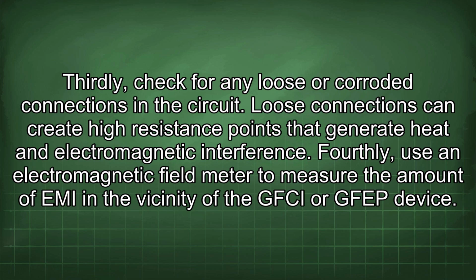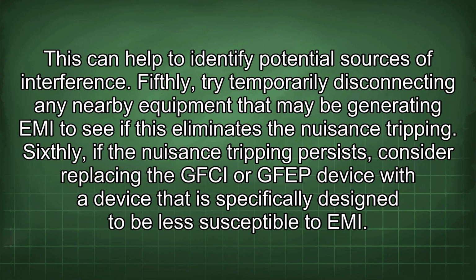Thirdly, check for any loose or corroded connections in the circuit. Loose connections can create high resistance points that generate heat and electromagnetic interference. Fourthly, use an electromagnetic field meter to measure the amount of EMI in the vicinity of the GFCI or GFEP device. This can help to identify potential sources of interference. Fifthly, try temporarily disconnecting any nearby equipment that may be generating EMI to see if this eliminates the nuisance tripping. Sixthly, if the nuisance tripping persists, consider replacing the GFCI or GFEP device with a device that is specifically designed to be less susceptible to EMI.